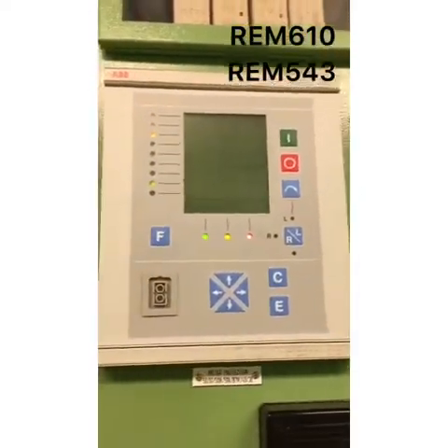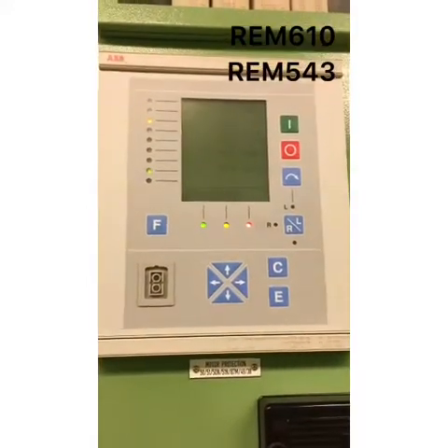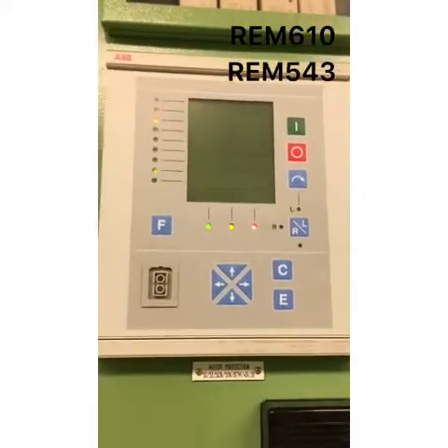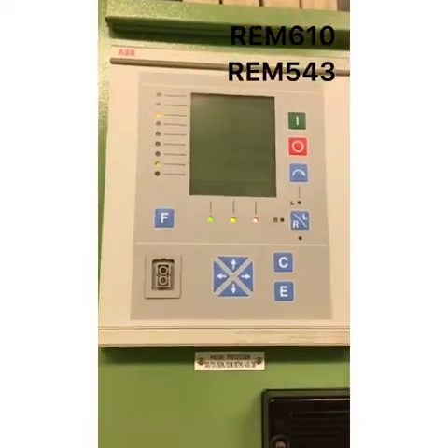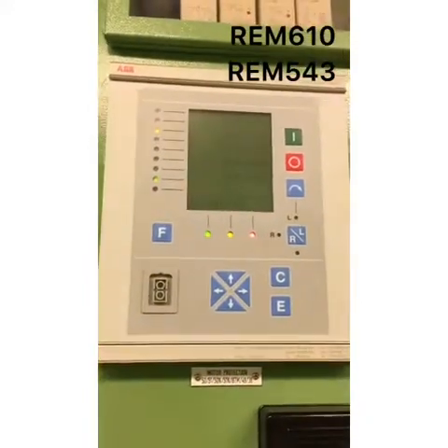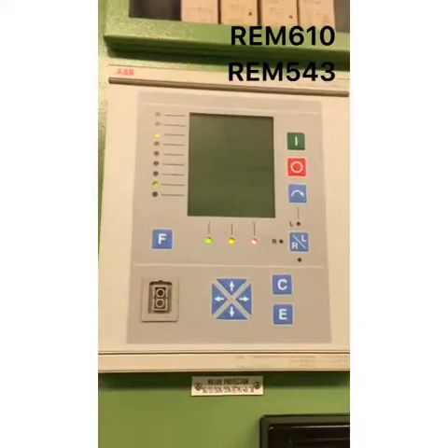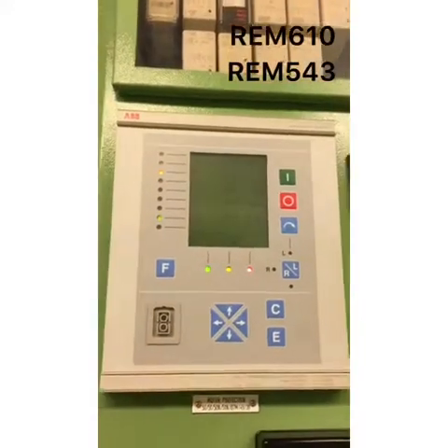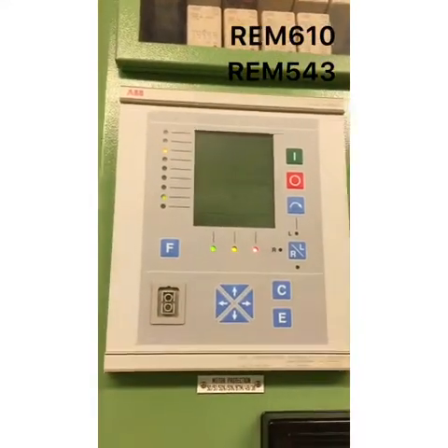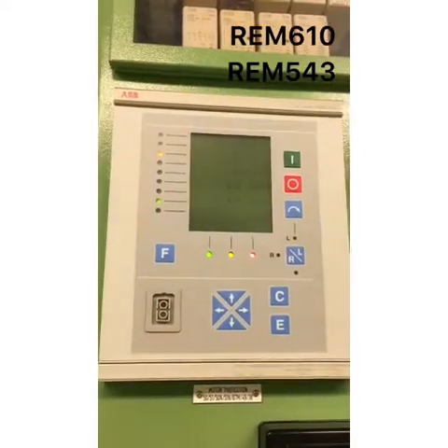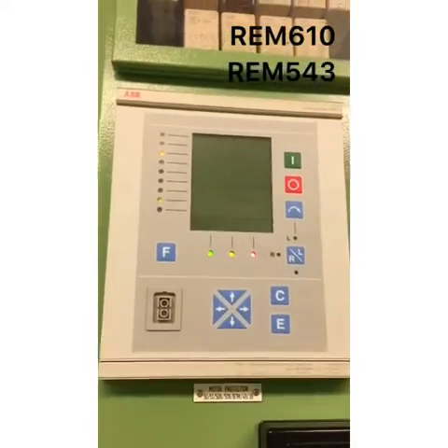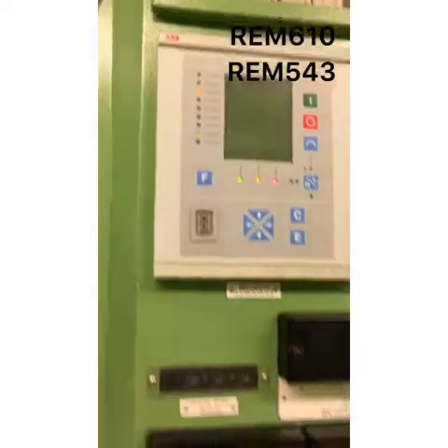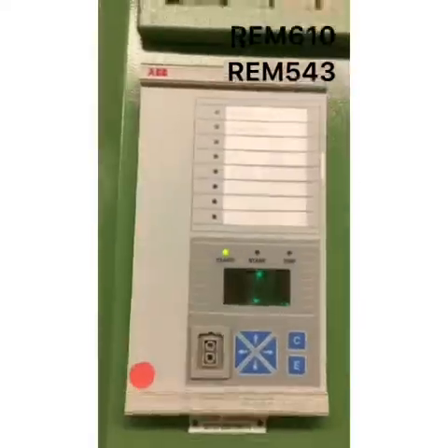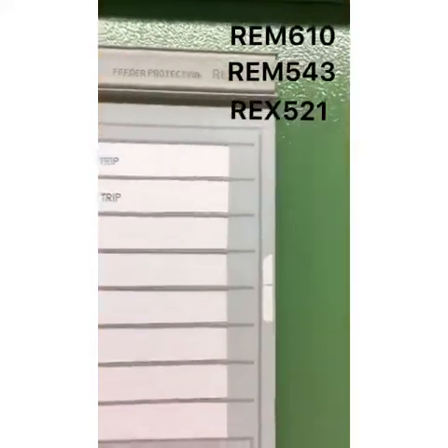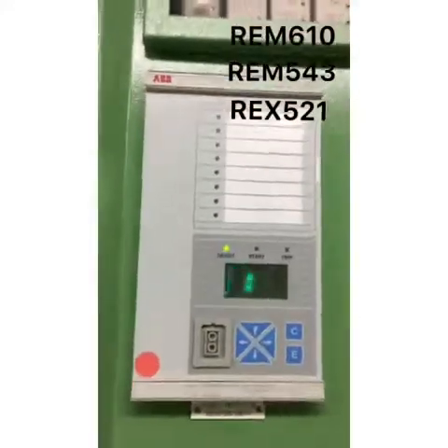The difference between these 2 relays is that this one contains more functions like differential, and we put these relays for important motors like boiler feed water pump, ID fan, because they have high rated power. And we have the REX521, which is for transformers.